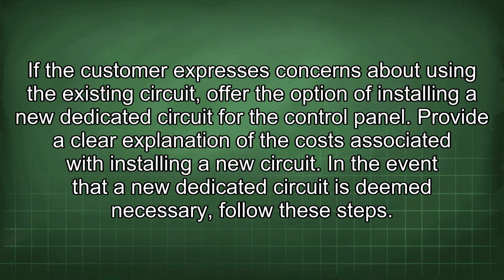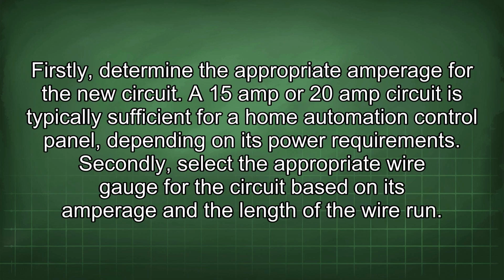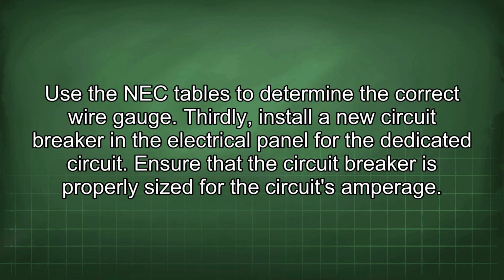In the event that a new dedicated circuit is deemed necessary, follow these steps. Firstly, determine the appropriate amperage for the new circuit. A 15-amp or 20-amp circuit is typically sufficient for a home automation control panel, depending on its power requirements. Secondly, select the appropriate wire gauge for the circuit based on its amperage and the length of the wire run. Use the NEC tables to determine the correct wire gauge. Thirdly, install a new circuit breaker in the electrical panel for the dedicated circuit. Ensure that the circuit breaker is properly sized for the circuit's amperage.